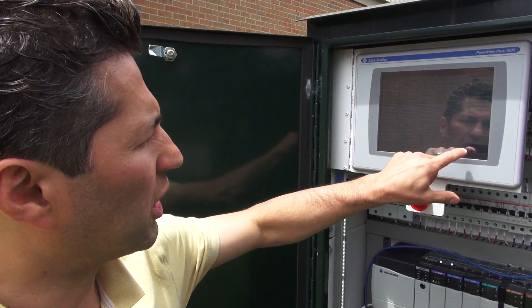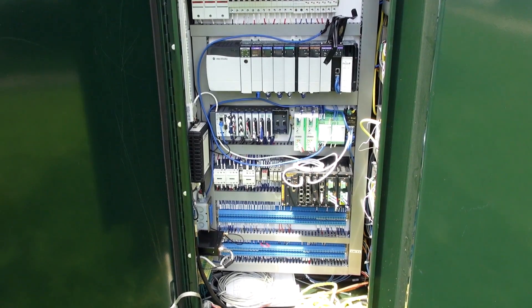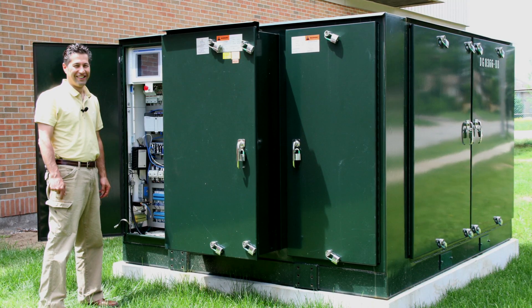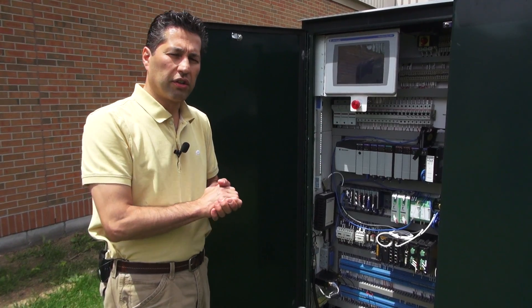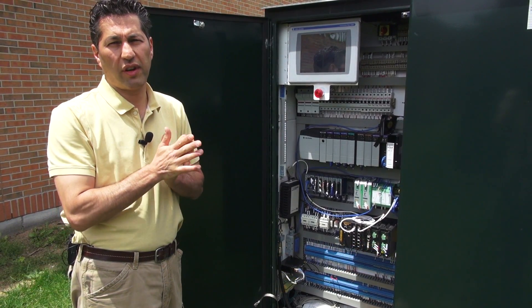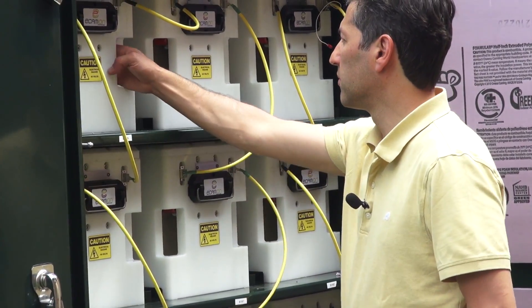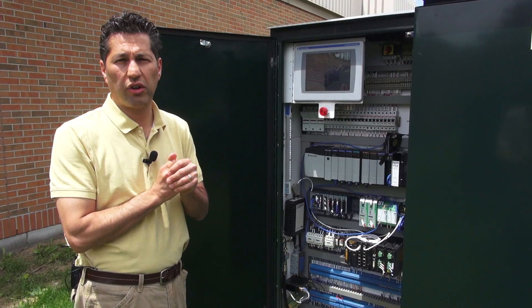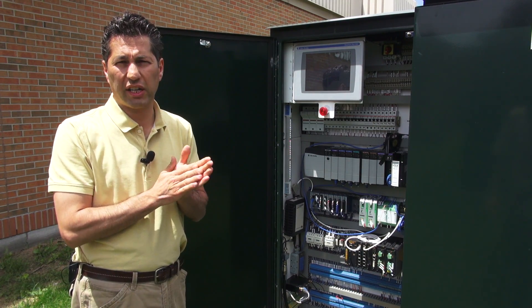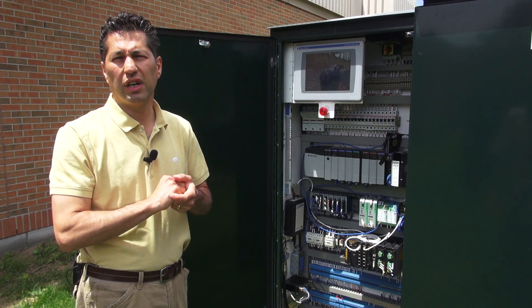The first is eCamion's community energy storage project, which is being tested out in North York near Toronto right now. It uses a piece of technology that we're all familiar with, the lithium-ion battery. The battery unit is where all the battery modules are stored, and the unit has 500 kilowatts of power and 250 kilowatt hours of energy. Inside the cabinet are all the battery modules with over 1,700 battery cells, integrated into one package, able to deliver with all the electronic controls powered to the grid.